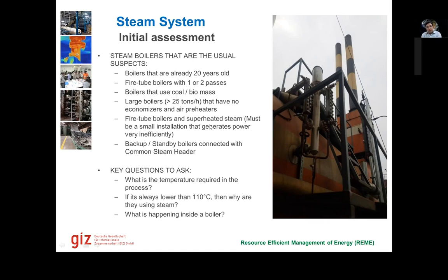Then larger boilers, 20, 30, 40 tons per hour boilers, and who don't have economizers or air preheaters. Even boilers with 5 or 10 tons per hour have big saving potential if we install economizers or air preheaters. But these become even more cost effective and even more feasible when we have bigger boilers. When we have boilers of 25, 30 or 40 tons per hour, we also need to see why the factory is still using low pressure or not using superheated steam and producing energy, and only producing steam separately and power separately.